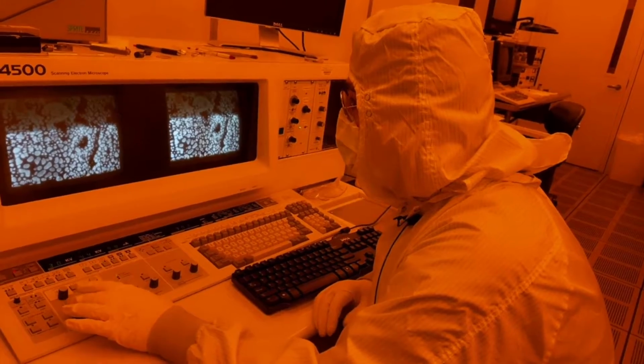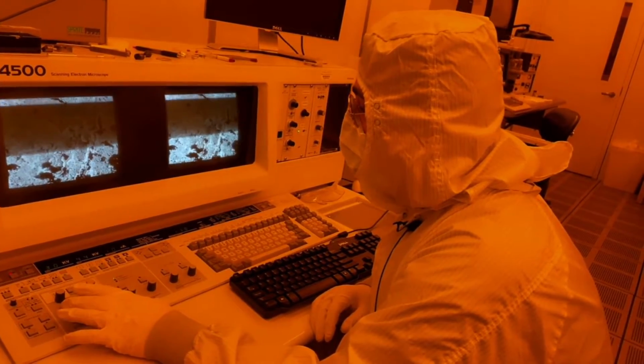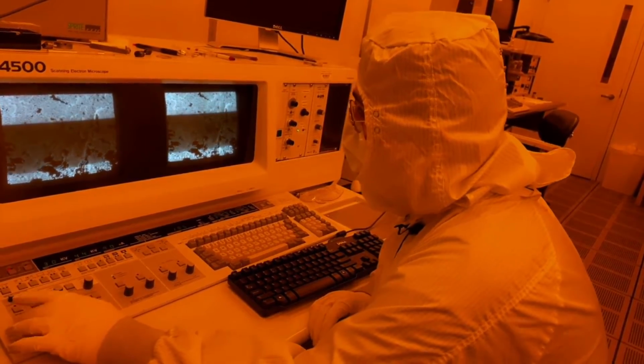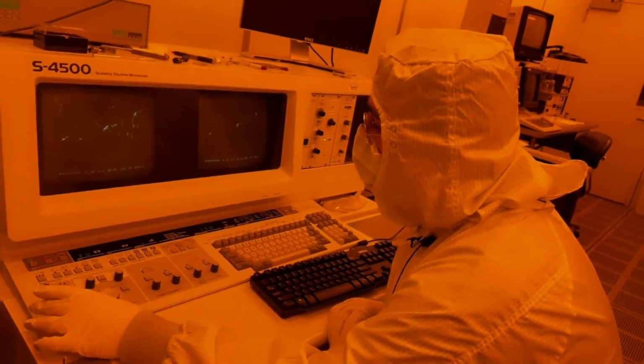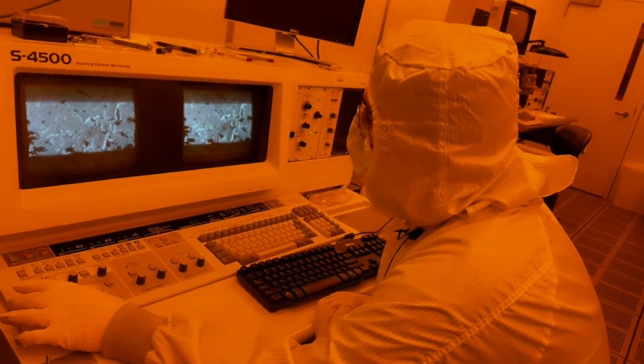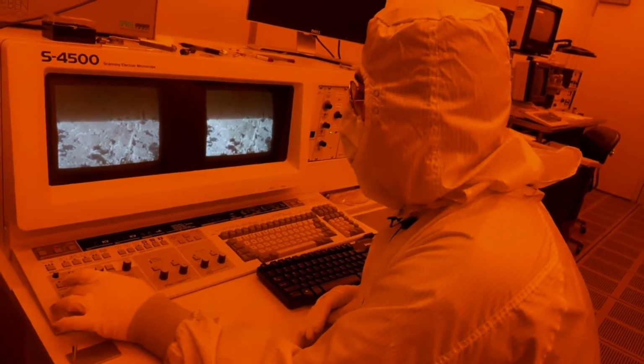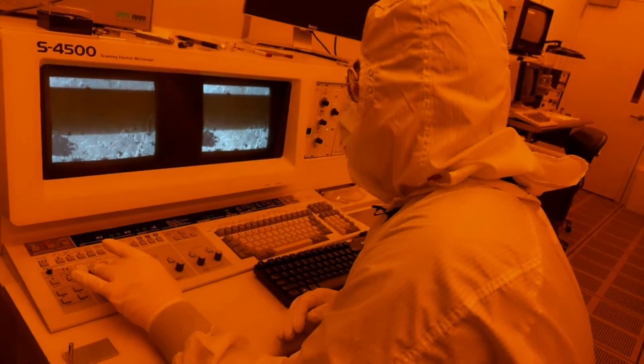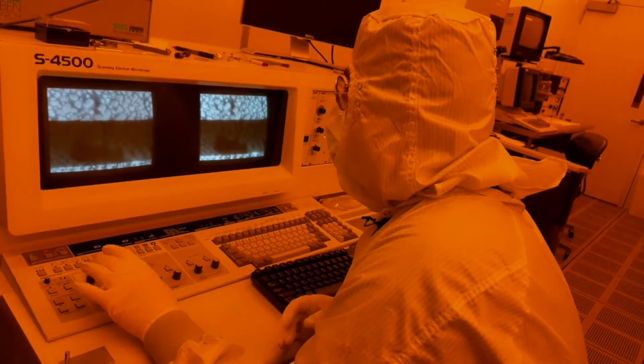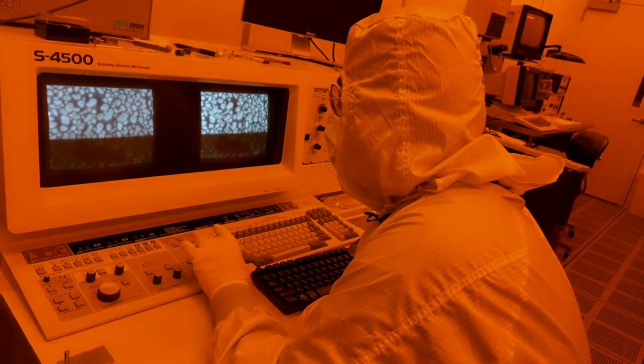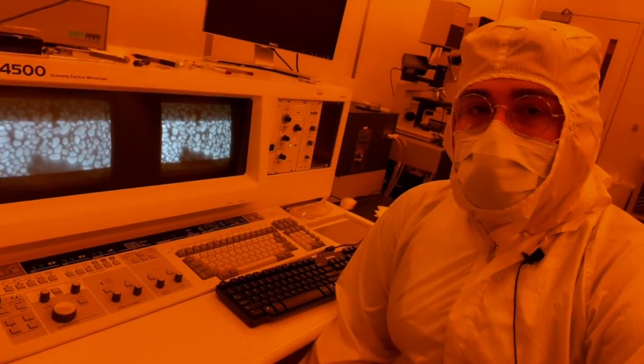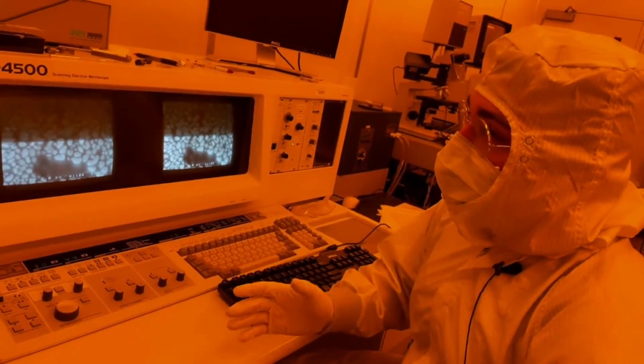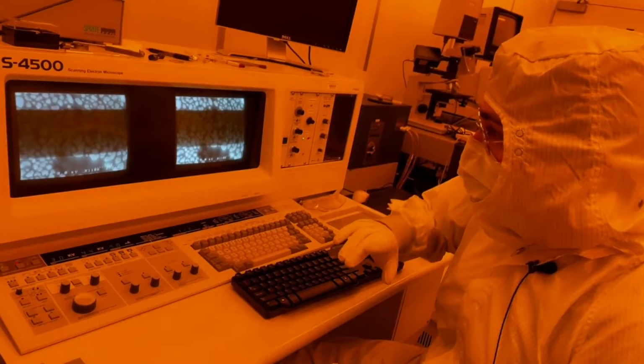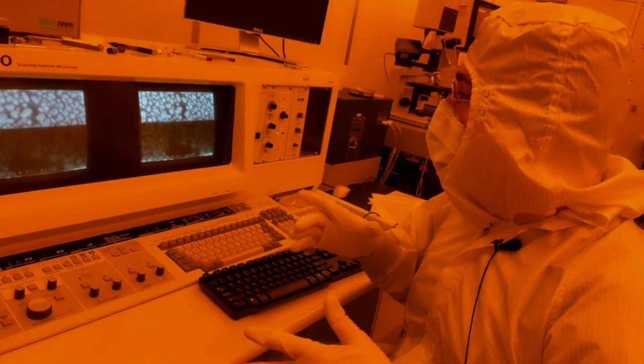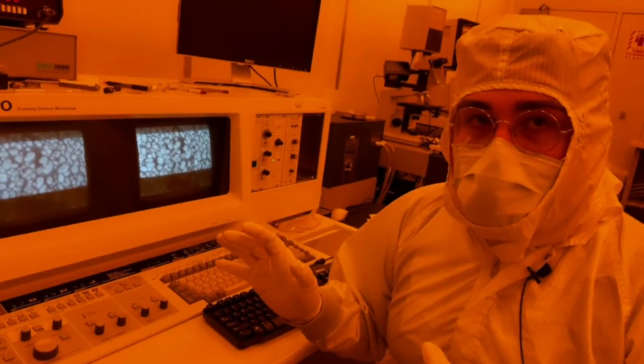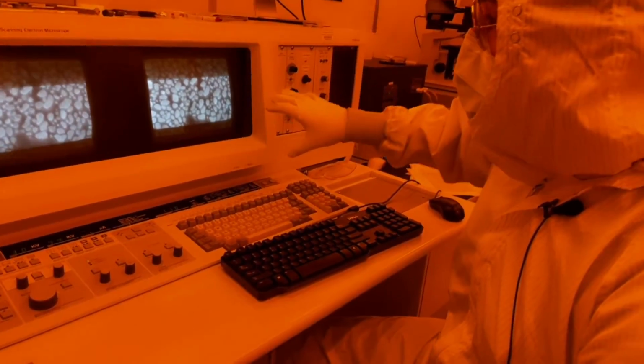The next thing that we can do, I'm going to zoom out, and we're going to change the brightness and contrast. So in this image, the contrast seems kind of high, so I'm going to turn the contrast down and turn the brightness up. When you do this, your image will be more of a grayscale, which is especially useful when you're trying to look at 3D structures. If you have a very high contrast, you'll just be able to see the top of the structure and the bottom of the structure, and you won't see any of the actual topography of the sample. So the more grayscale your image is, the more easily you'll be able to see the topography.